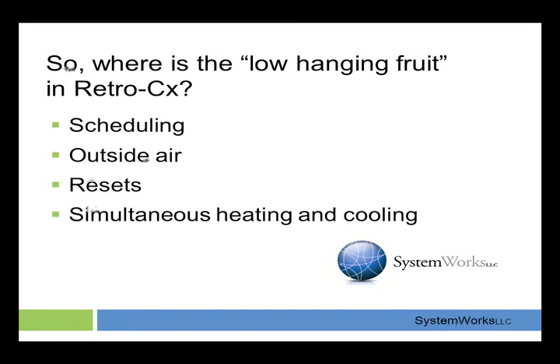Resetting duct static and discharge air static based on the controllability of the building automation system. The building automation system can look at the demand and say, no, we don't need 55-degree air. It can warm up to 57 or 58 degrees and save energy. It's that powerful, and that's what you have to take advantage of. And again, if you have any simultaneous heating and cooling going on, eliminating that is a very cost-effective way to make the equipment perform better, last longer, and save energy.